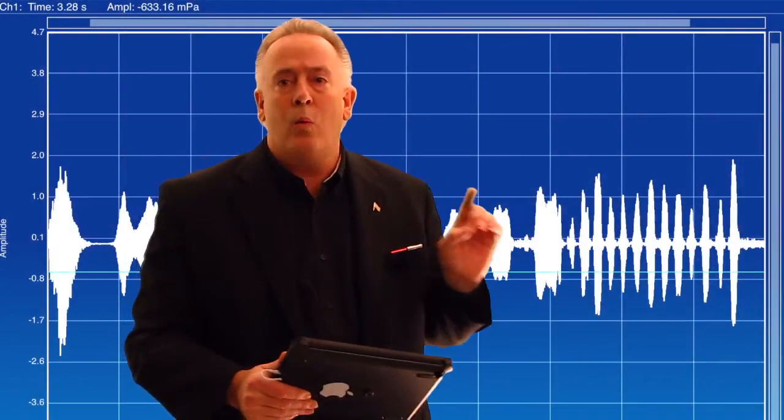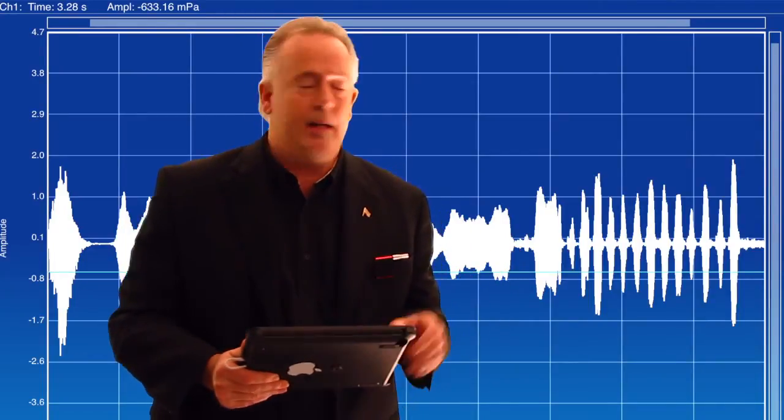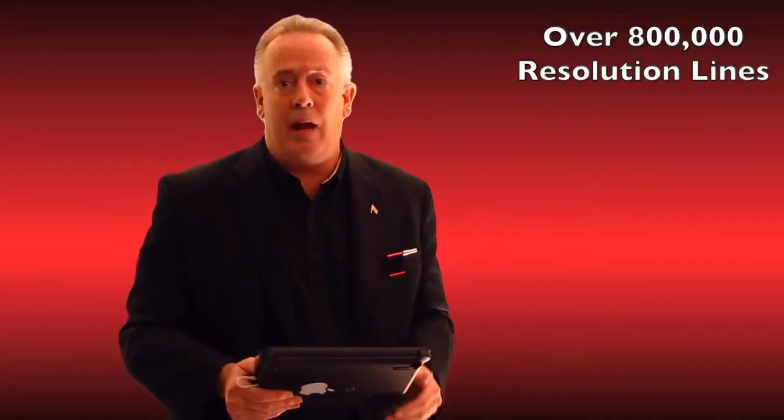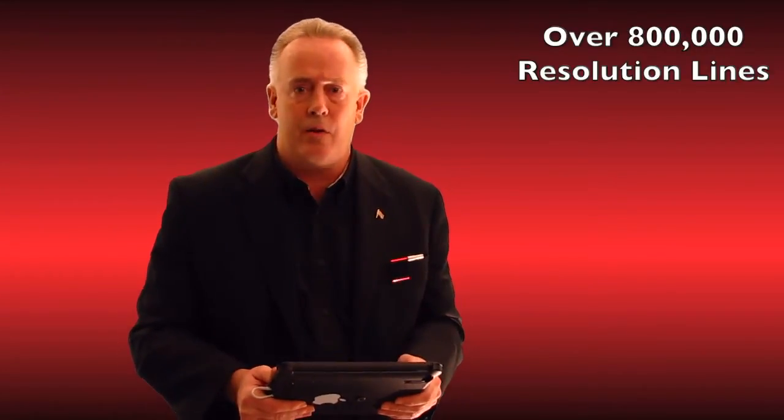In our advanced app, we're able to record 20 seconds of 44 kilohertz-per-second data that will equate to very close to a million lines and enable 0.03 hertz resolution. So this can really compete with any heavy-duty analyzer on the market.